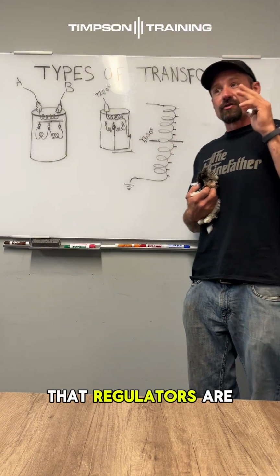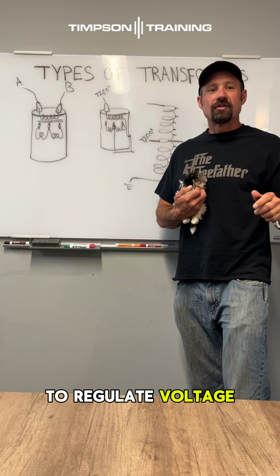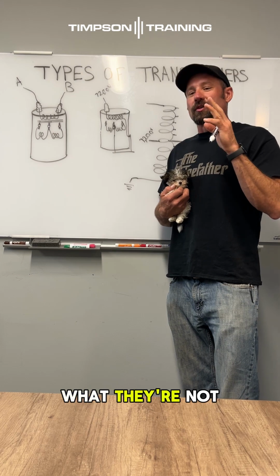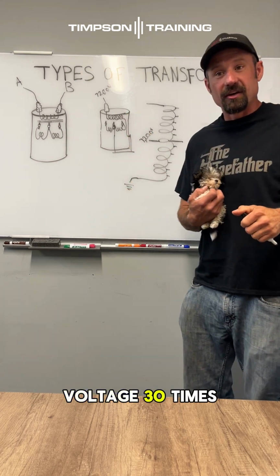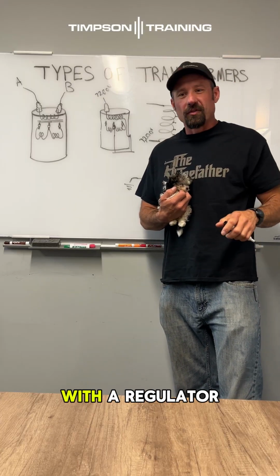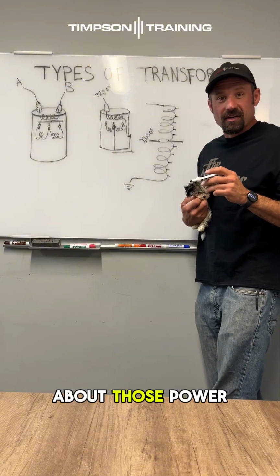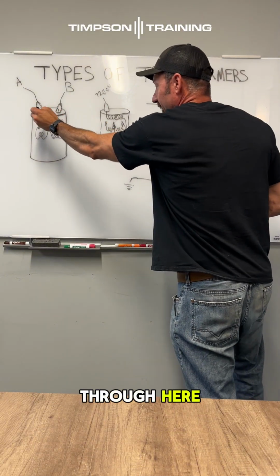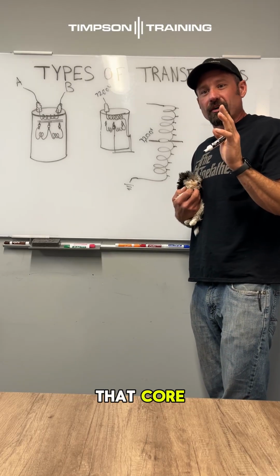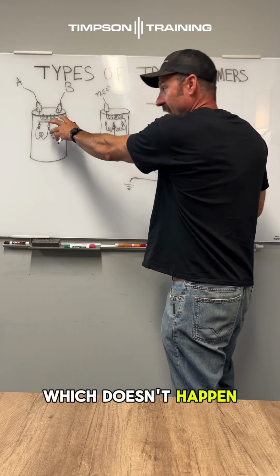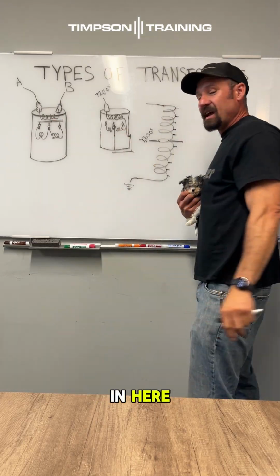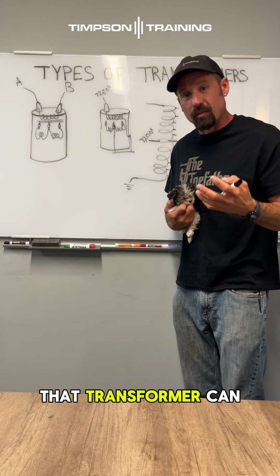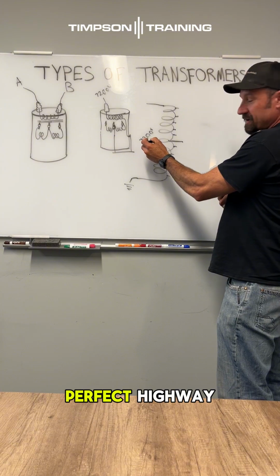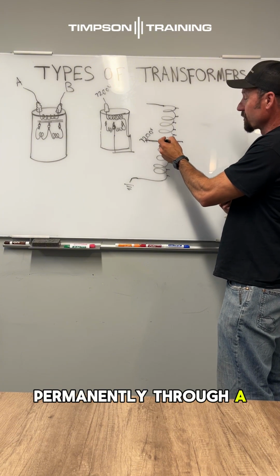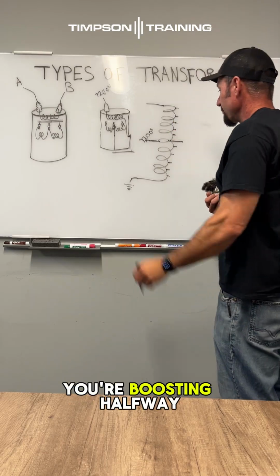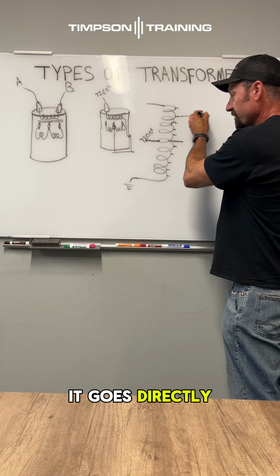It's worth saying that regulators are a great and easy way to regulate voltage on long runs of voltage drop. What they're not good for is stepping down voltage 30 times. The rule of thumb is you can do 2 to 1 with a regulator, and that's because we were talking about those power surges. Power surge coming through here has to be able to magnetize that core at the same rate that that power surge is happening, which doesn't happen in an isolation transformer. It does happen in here, but it's limited by how much pressure that transformer can take. Here, it makes a perfect highway because it's attached permanently through a coil. So if your tap changer's up here, you're boosting halfway and you get a power surge, it goes directly through.